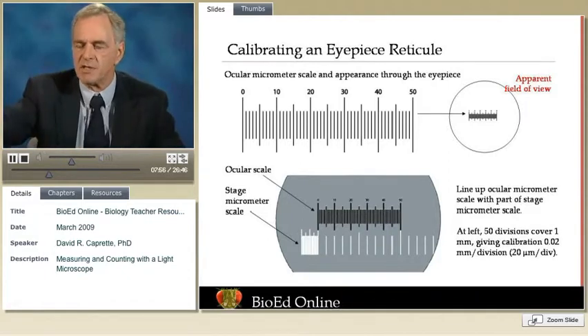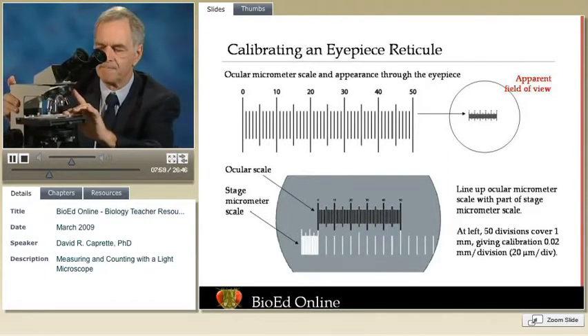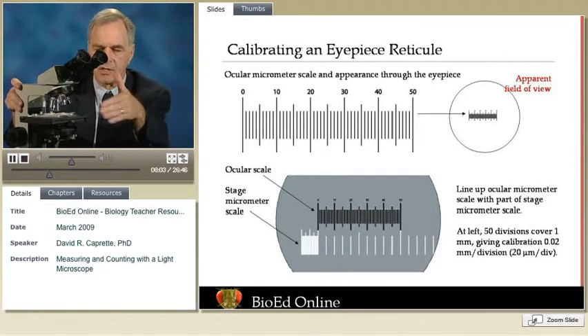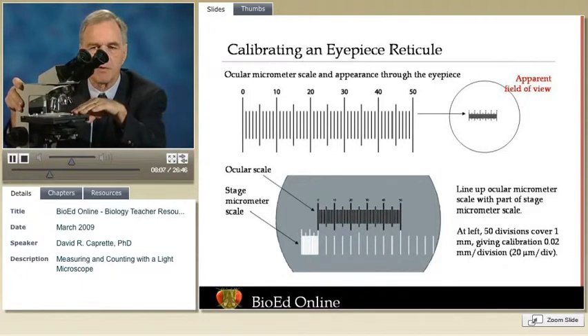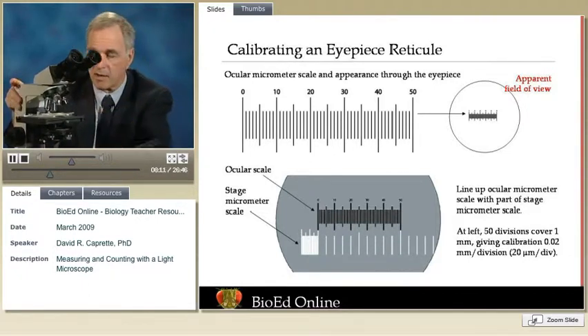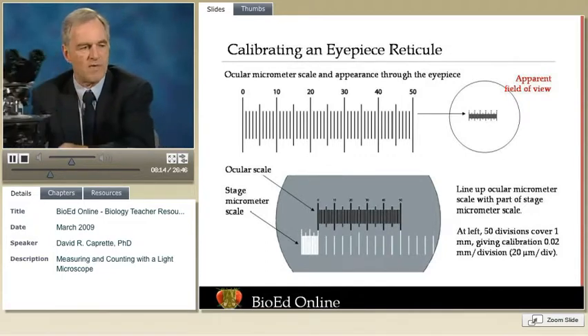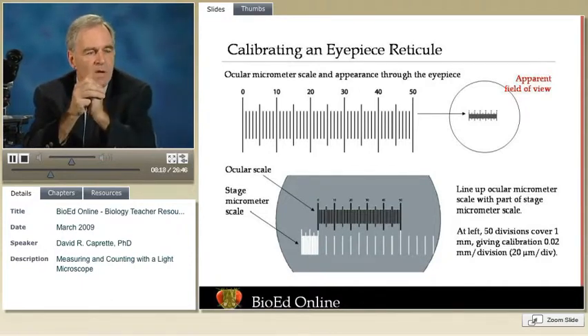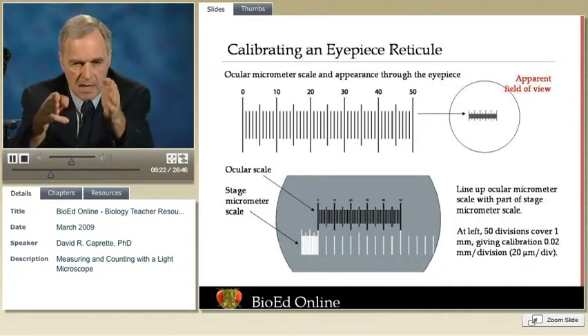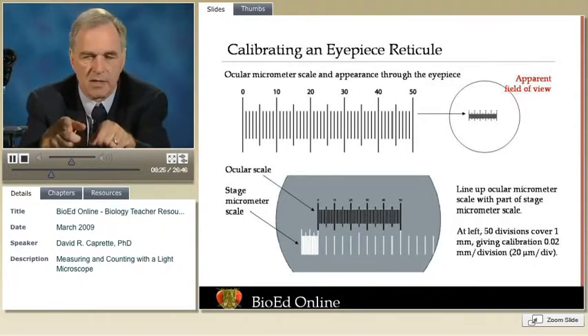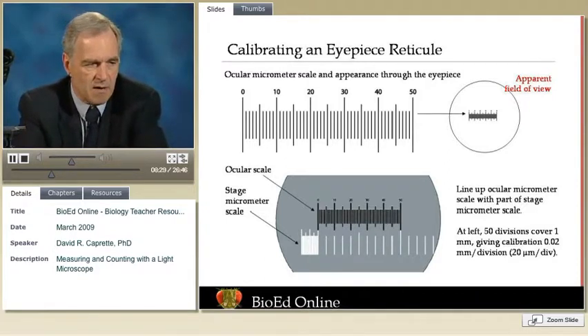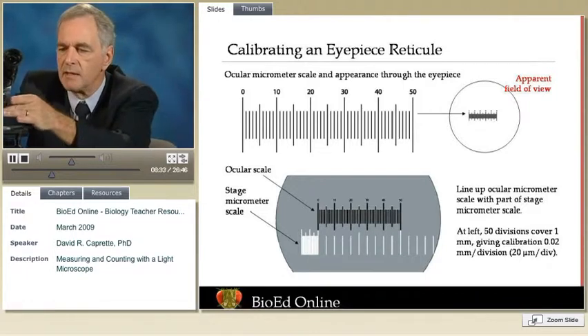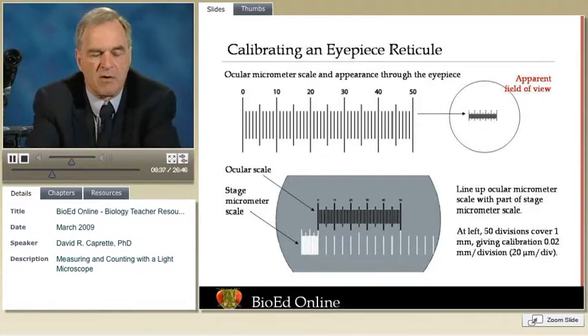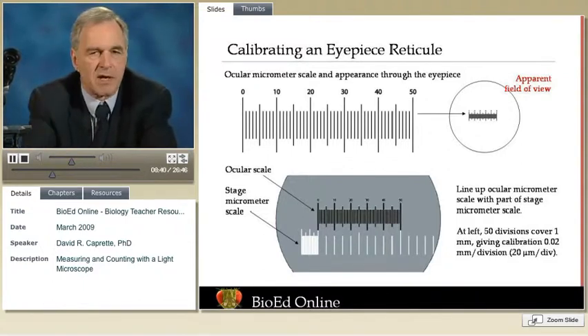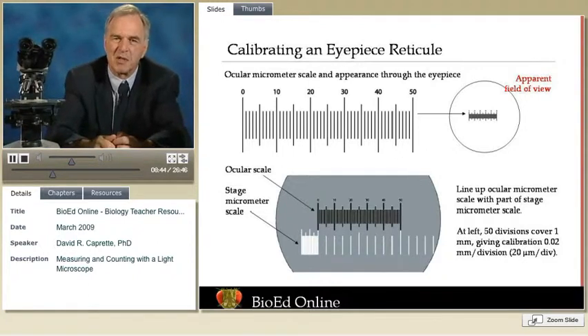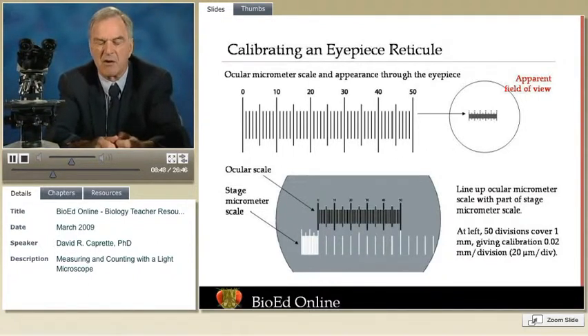To calibrate an eyepiece reticle, we take our stage micrometer and use the mechanical controls to center up the scale so that the eyepiece reticle is superimposed over the micrometer scale. We then line up the divisions of the reticle with the divisions on the micrometer scale, so that we can get a relationship between divisions on the reticle and divisions on the scale. In the example here, we were at 40 power, and the reticle is a 50 division reticle. It covered exactly 1 millimeter length of the stage micrometer. That gives us a calibration of 0.02 millimeters per division, which is the same as 20 micrometers per division.